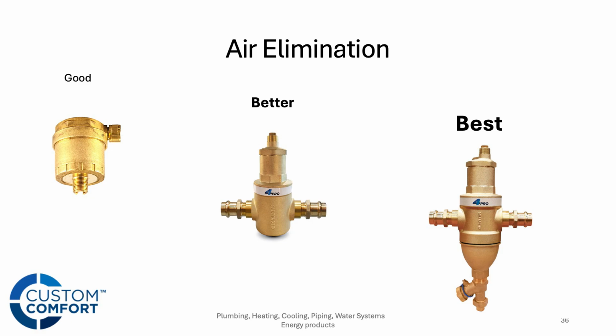And the nice part about the air elimination and the air dirt combo, it's essentially the same body, right? So the air eliminator, we've just added a dirt separator on the bottom with a magnet. It's going to be the same stainless steel coalescing media inside of it that really helps remove any of the air that's in the system. Again, if you don't purge the air out of these, you're going to have problems. Set yourself up for success with that better, best type of air elimination there.